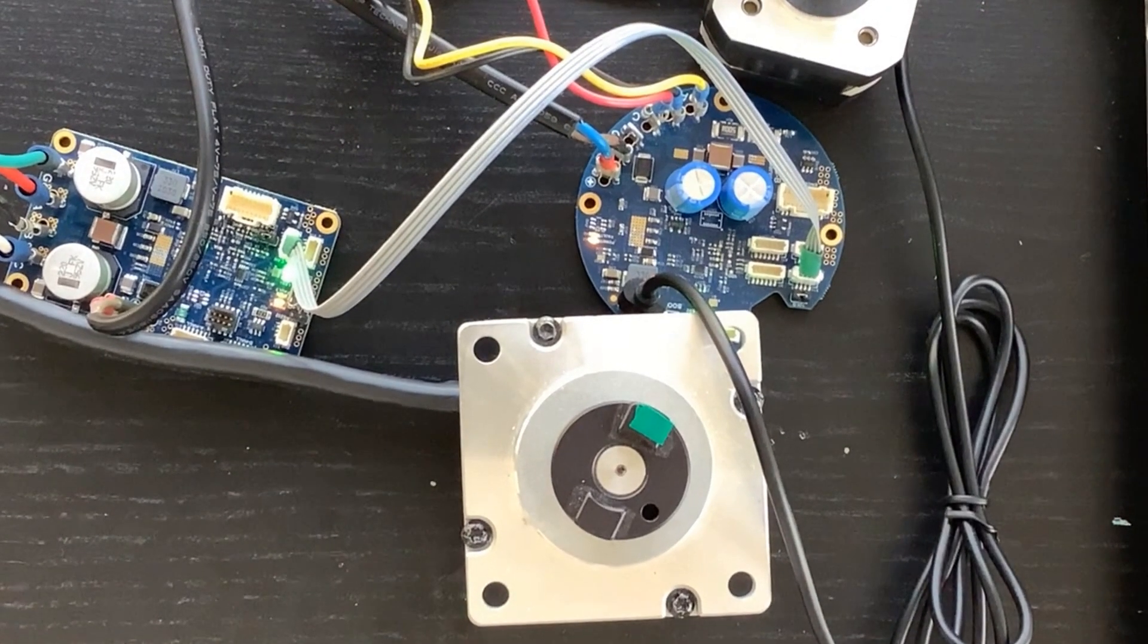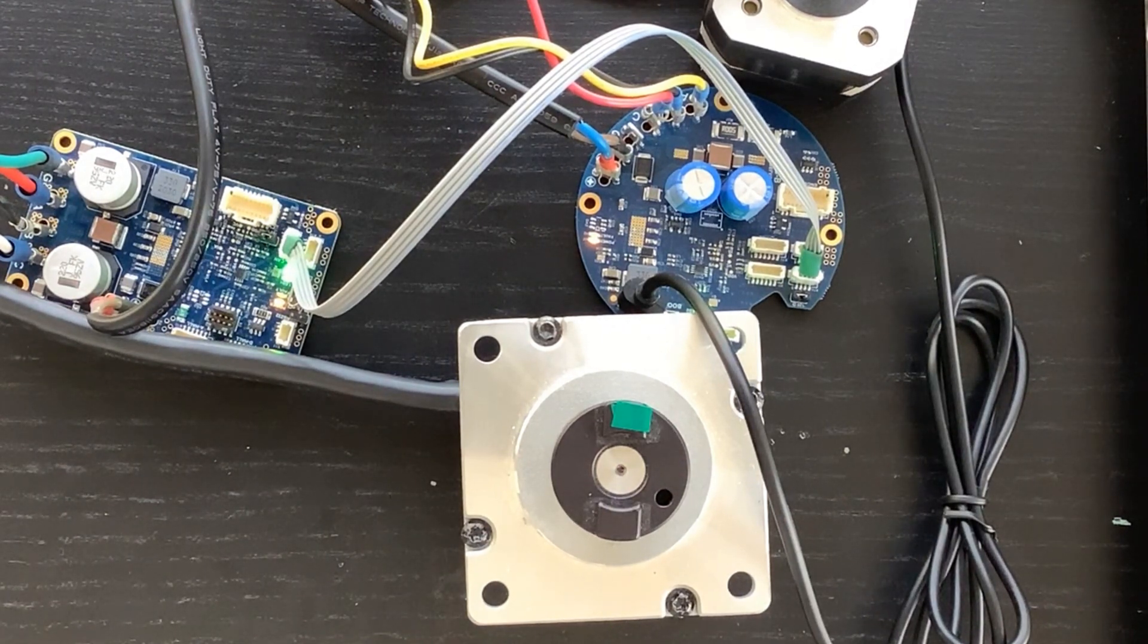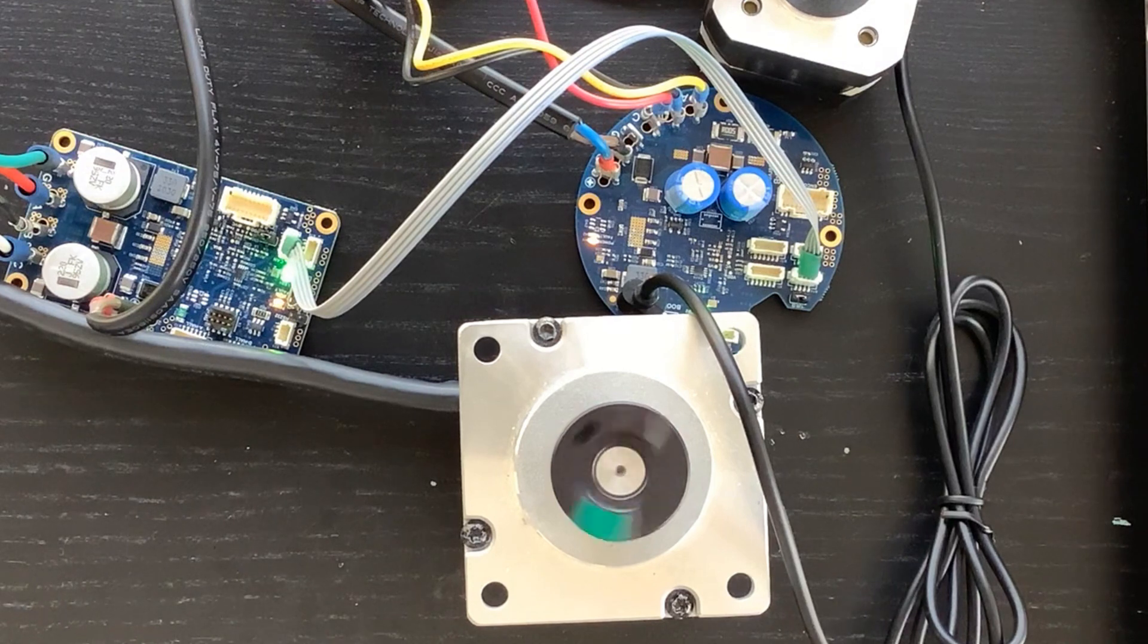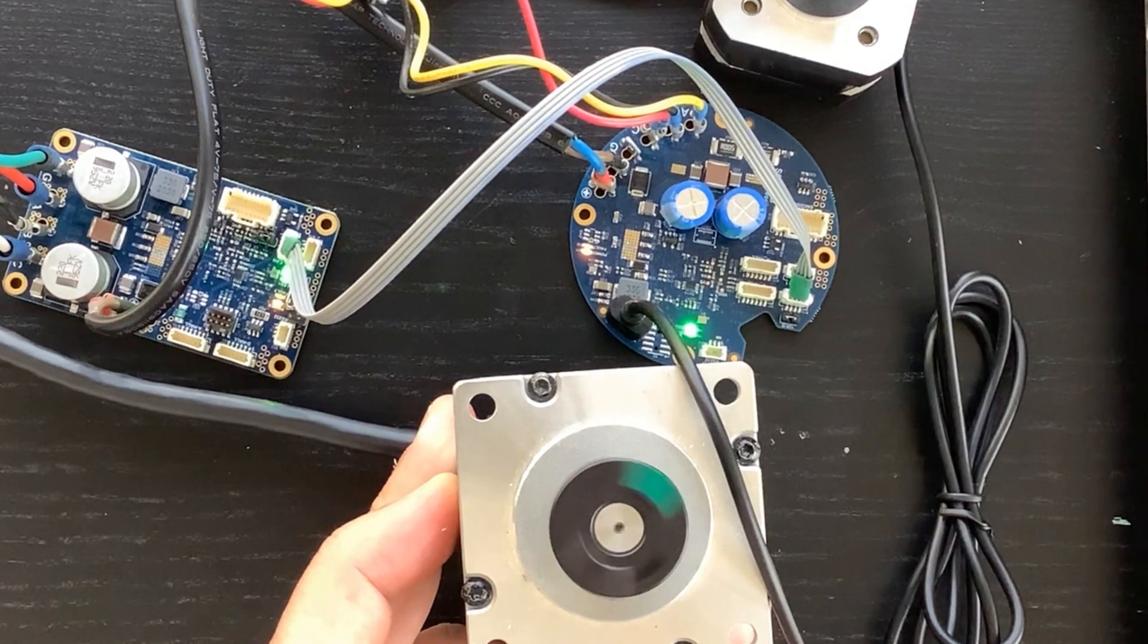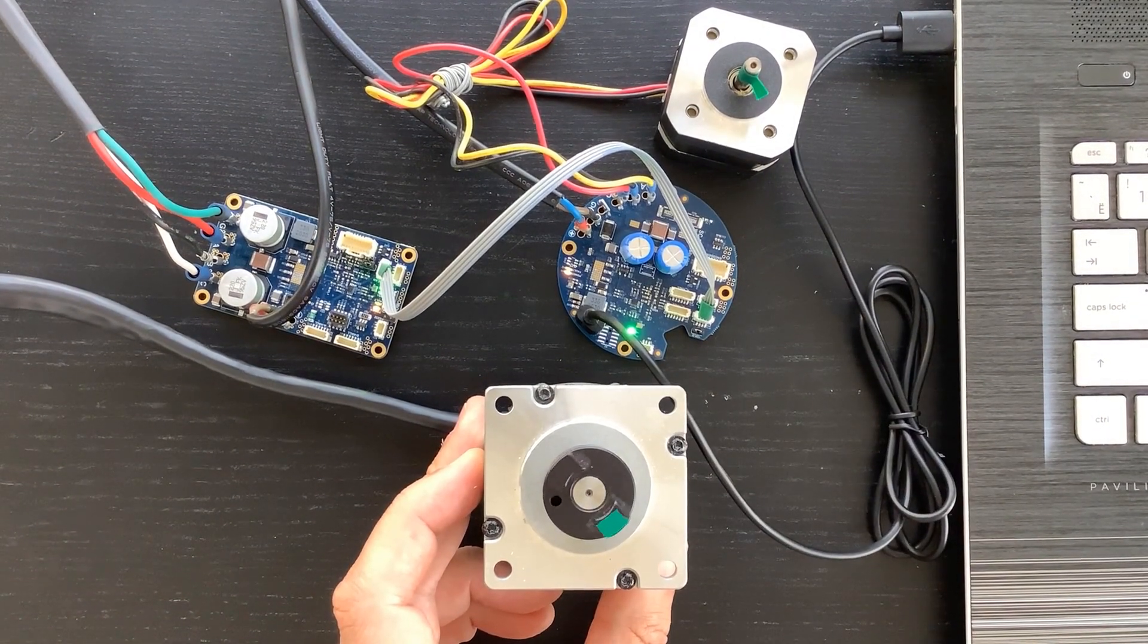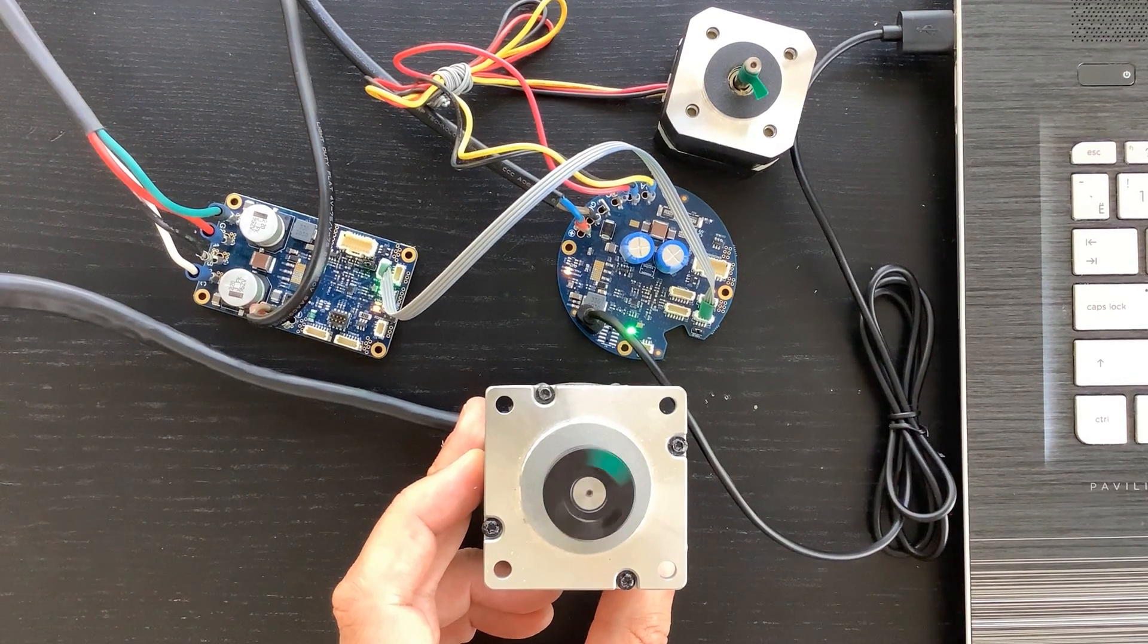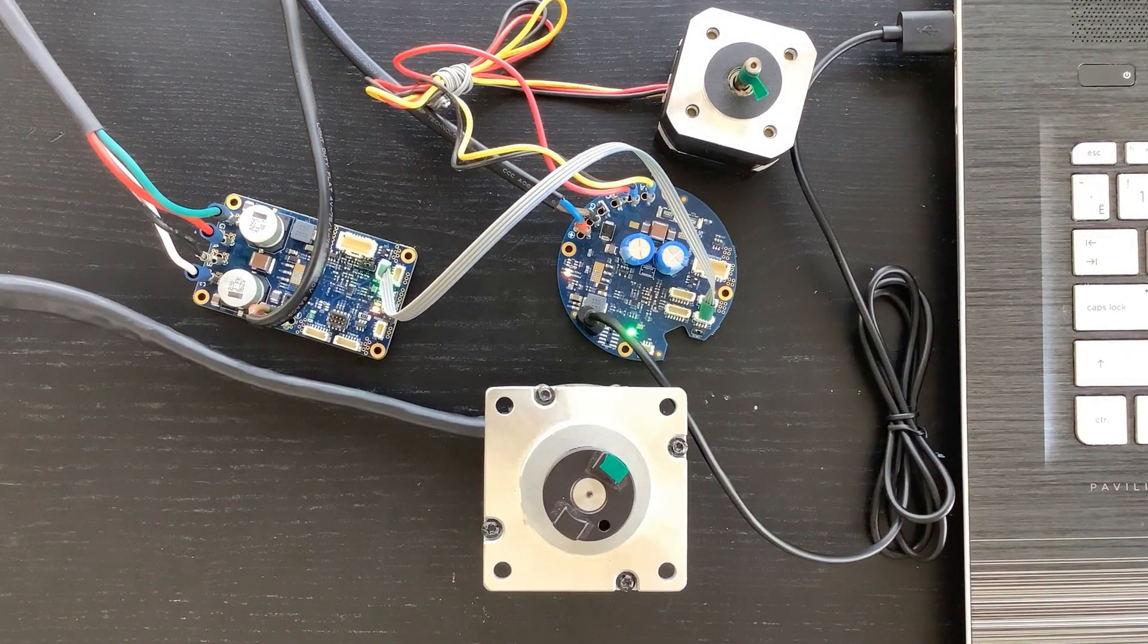Note that the motors produce a beep sound at the beginning of the auto configuration routine. The controller sends probing electric pulses to the motor to measure various characteristics of the motor. The beauty of the auto configuration function is that the controller automatically configures itself when commissioning a new motor. Beware of the rapid accelerations of the motor that might take place a few times. I suggest that you watch a separate video dedicated to peculiarities of the auto configuration routine. The motor produces the second beep sound to indicate the end of the auto configuration procedure.